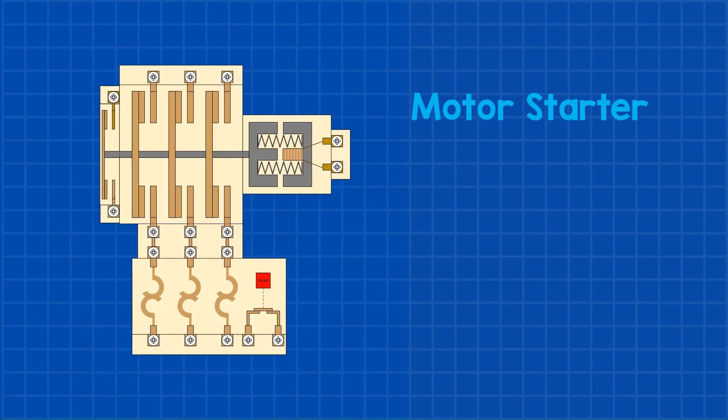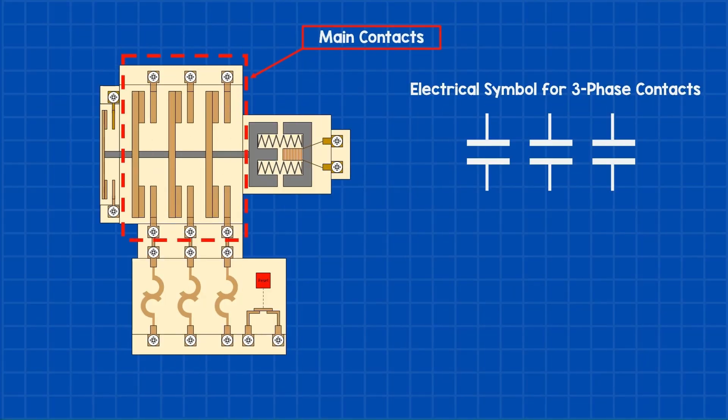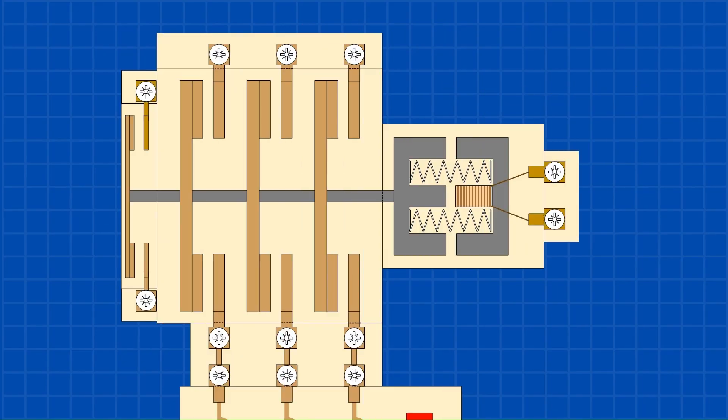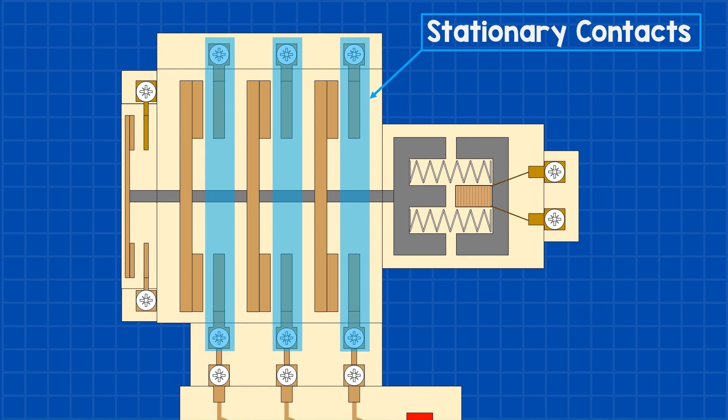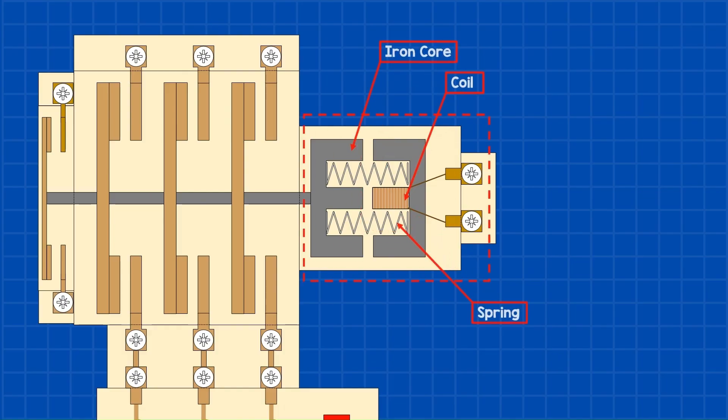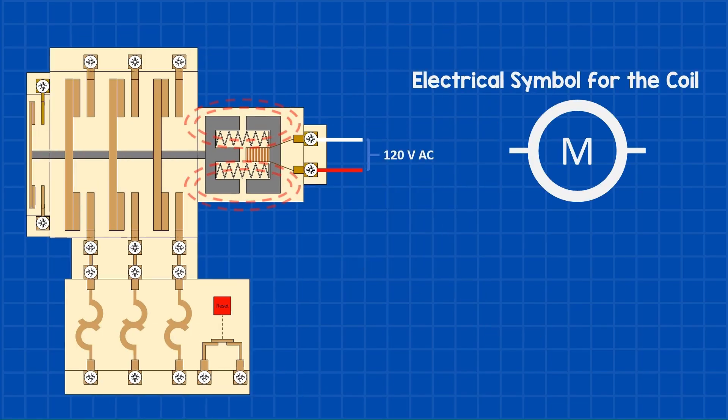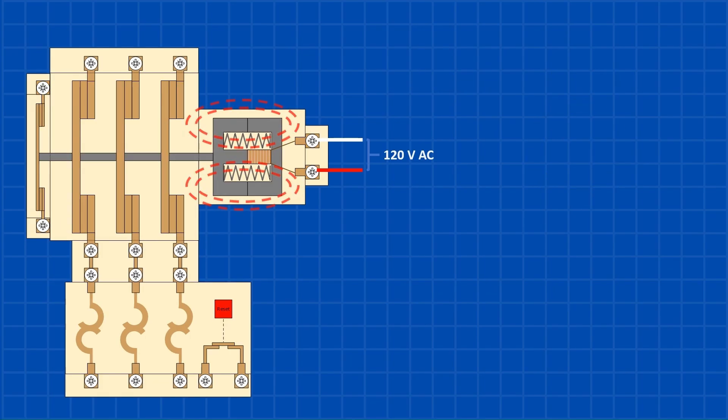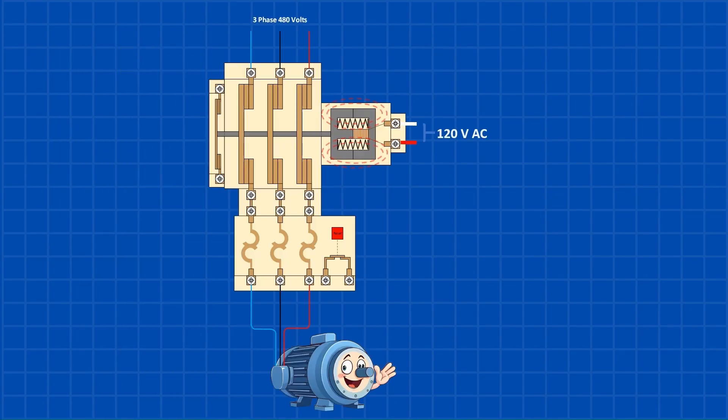But how does a motor starter work? First, the motor starter contains three sets of contacts that deliver power to the motor. Each set of contacts consists of a stationary and a movable contact. The movable contacts are attached to the coil with non-conductive materials like fiberglass or reinforced molded plastic. The coil typically consists of three main components: an iron core, a main coil, and springs. When the correct voltage, 120 volts AC in this case, is applied to the coil, it creates a magnetic field that draws in the iron core. This movement closes the contacts, enabling power to pass through them and the overload elements, which energizes the motor. The motor continues running until power is removed from the coil.